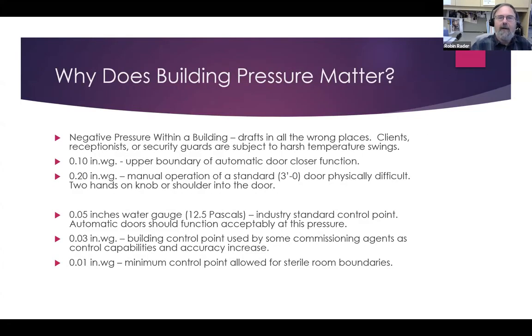I'm going to talk a little bit about static pressures within a building. Negative pressure within a building is a bad deal. It shoots drafts into all the wrong places. Clients or receptionists, security guards are all subject to harsh temperature swings. Some various pressure levels, 1/10 of an inch is the upper boundary where an automatic door closer can function. Elevator doors start to have trouble beyond a 1/10 of an inch, things like that.